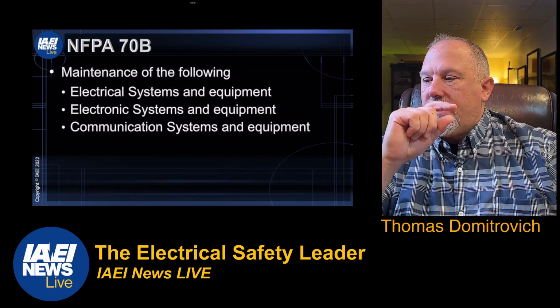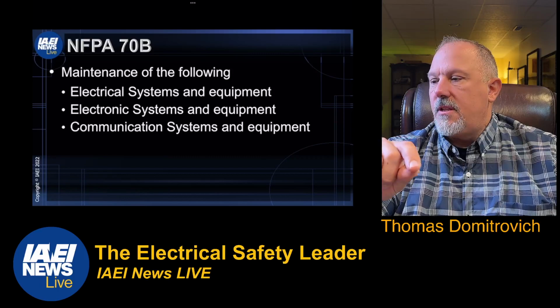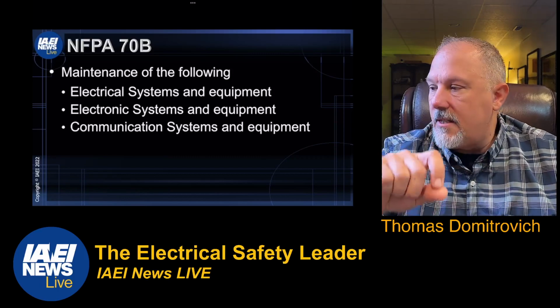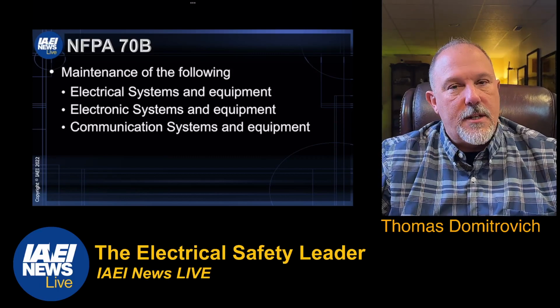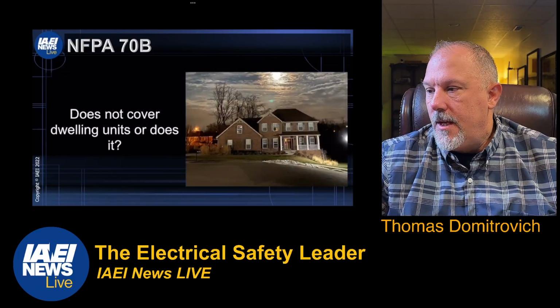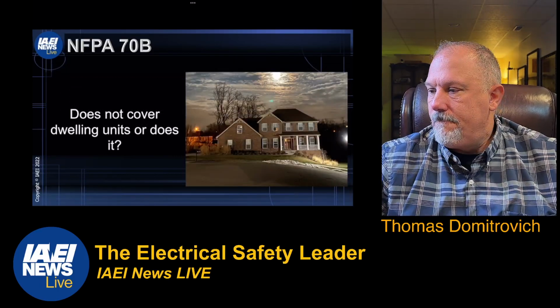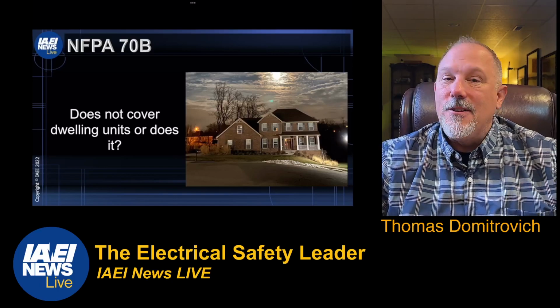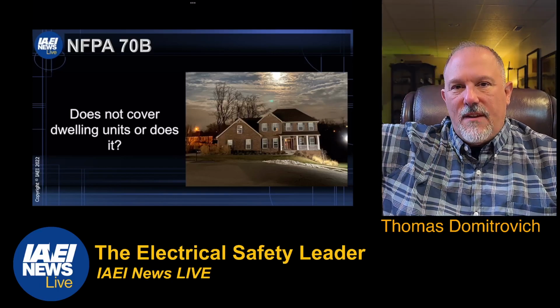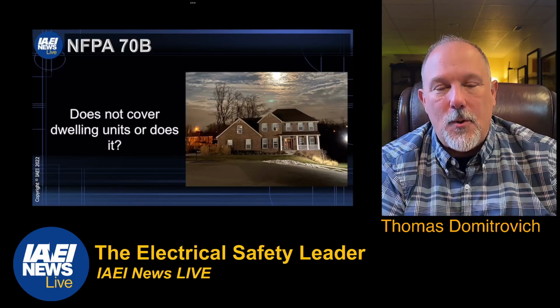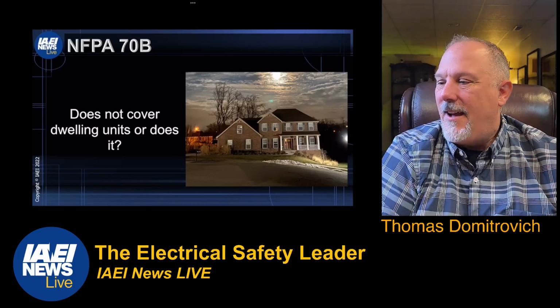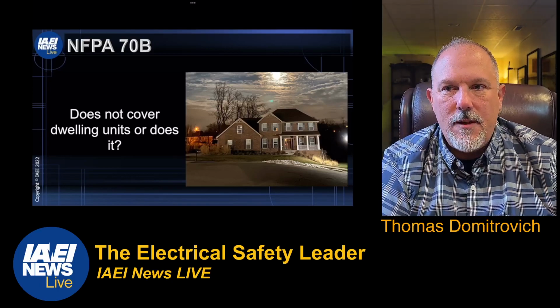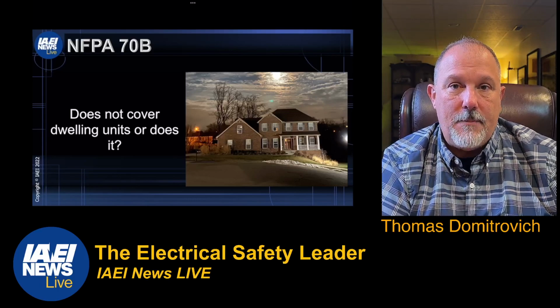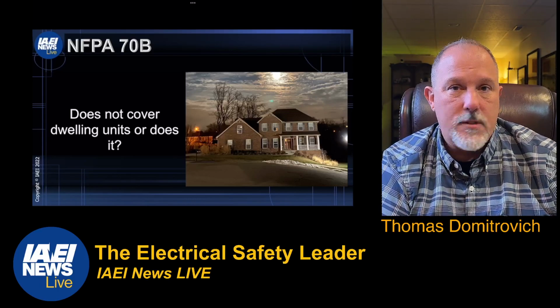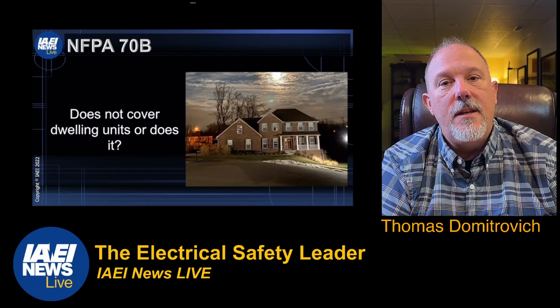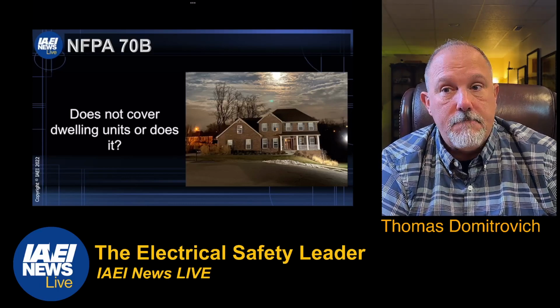70B tells us it covers maintenance of electrical systems and equipment, electronic systems and equipment, and communications systems and equipment, so it's pretty broad. It does not cover dwelling units. And the reason I say that, we had multifamily mentioned above, but in reality, in my opinion, a receptacle in my basement or living room is no different than a receptacle in an office in a commercial building. It's a receptacle.